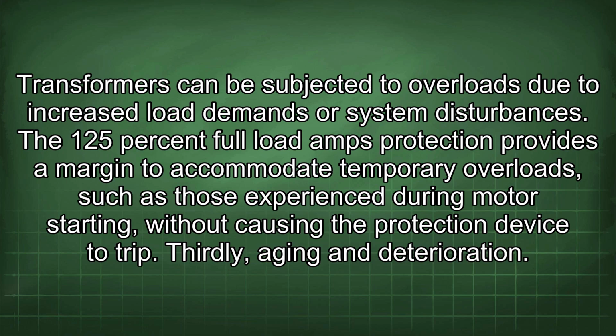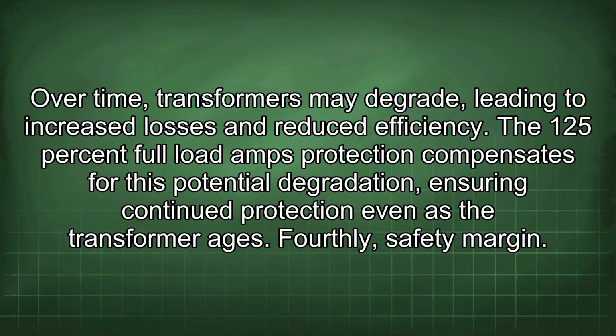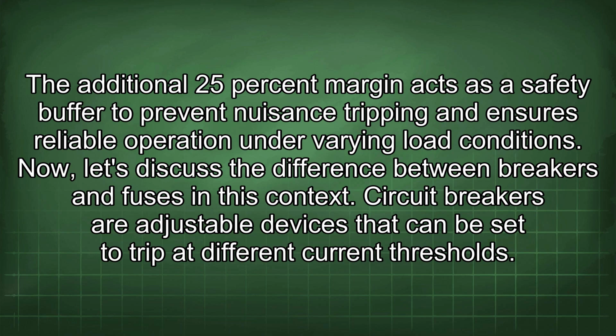Thirdly, aging and deterioration. Over time, transformers may degrade, leading to increased losses and reduced efficiency. The 125% full load amps protection compensates for this potential degradation, ensuring continued protection even as the transformer ages. Fourthly, safety margin. The additional 25% margin acts as a safety buffer to prevent nuisance tripping and ensures reliable operation under varying load conditions. Now, let's discuss the difference between breakers and fuses in this context.